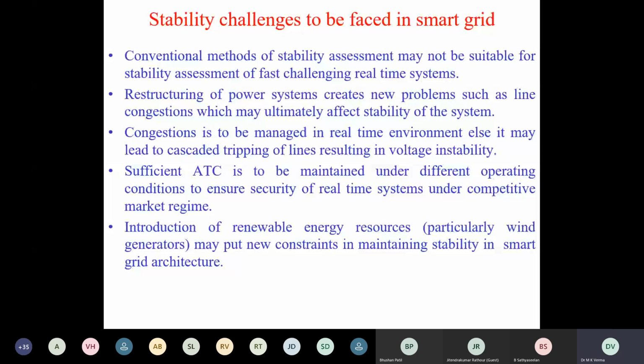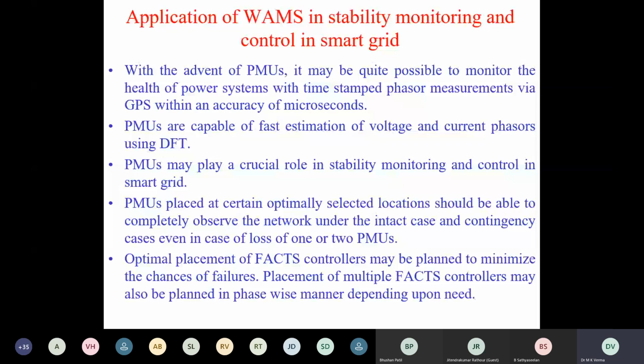Application of WAM. WAMs, wide area monitoring systems, may be quite helpful in stability monitoring and control through synchrophasor technology. We can put phasor measurement units at different locations, and these phasor measurement units, called PMUs in brief, are able to monitor completely the health of the power system with time stamped measurements. That is, at the same time you are getting measurements at different locations. Otherwise it will be of no use if measurements are not stamped.